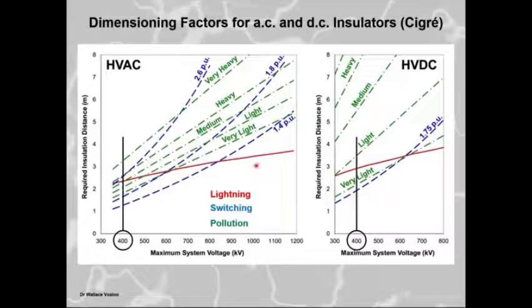Now, when we start looking at selecting insulators and whether pollution is a big issue or what parameter plays a big role, a study that was done in Cigré, which we were all very much part of, came up with these curves. In these curves, you'll see that the green is what insulation distance you need for different pollution levels at different voltage levels, and what insulation length you need for switching and what insulation length you need for lightning. Now, if you take a look at AC and compare it with DC, if we look at 400 kV AC, the one that plays a big effect on the insulation distance is switching and pollution.